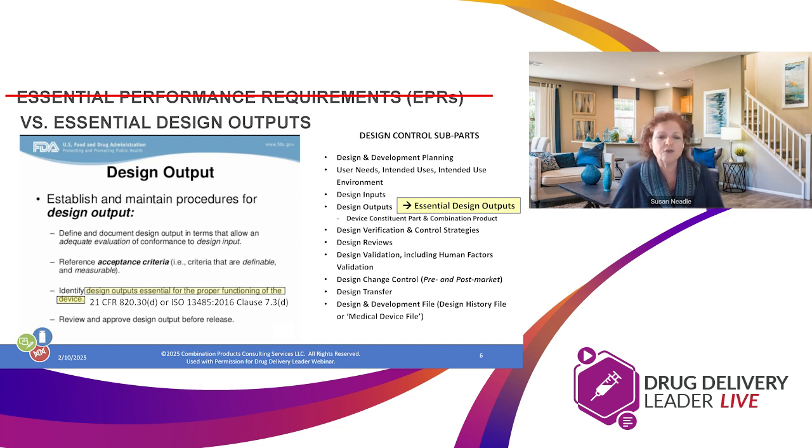And when you look at the FDA training that they even have available online, where they talk about what a design output is, one of the notes is that those are the outputs that have translated your technical design requirements into the finished product specifications and acceptance criteria, definable and measurable.